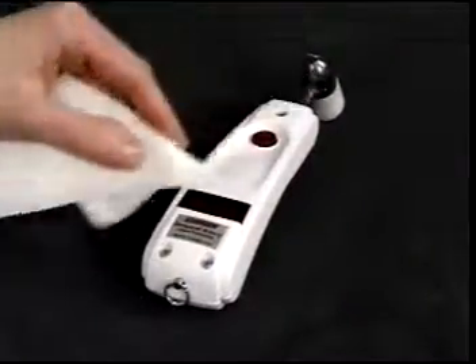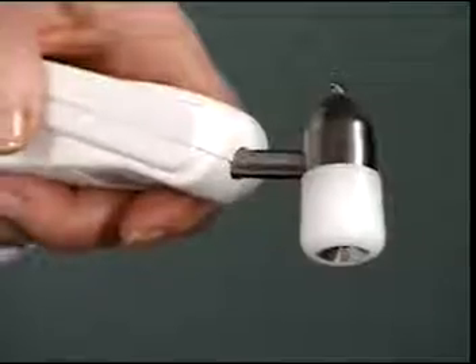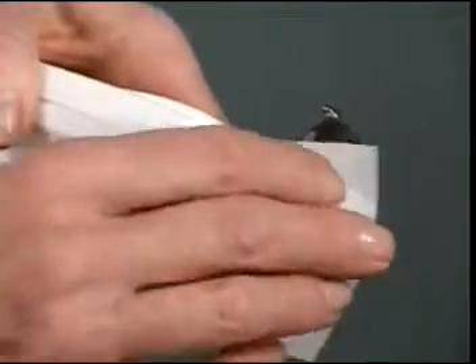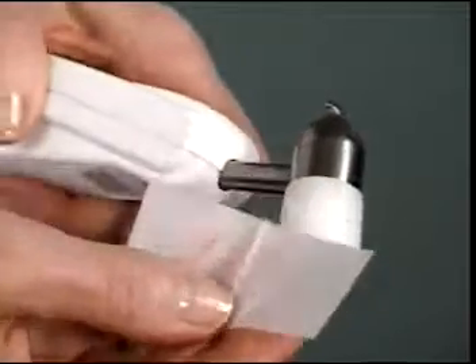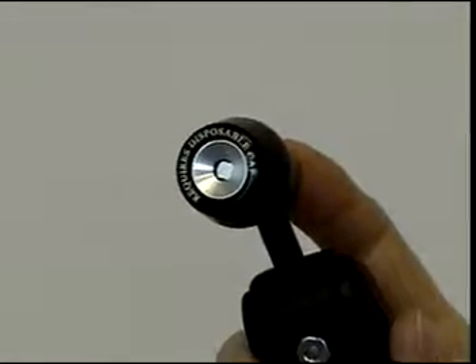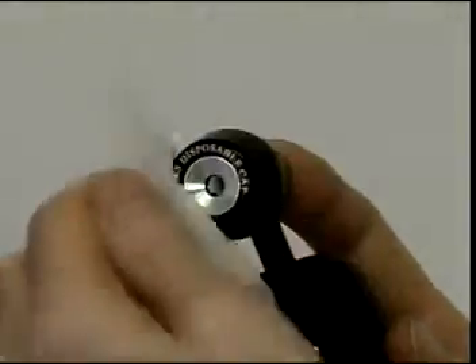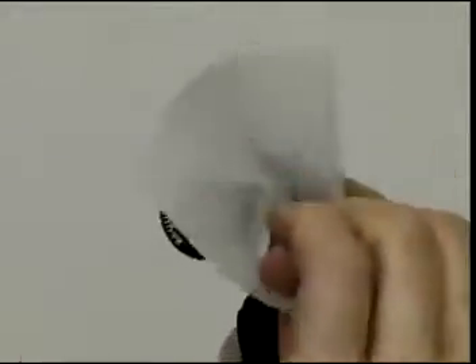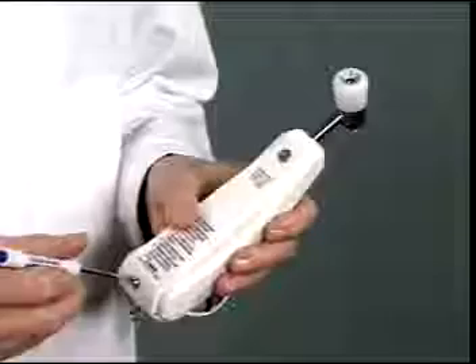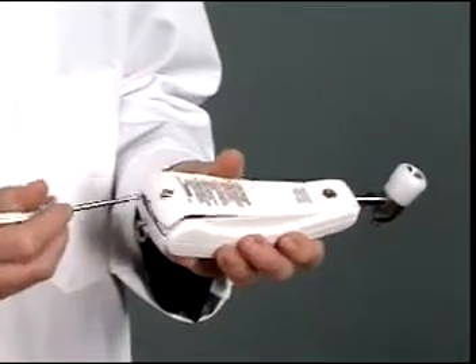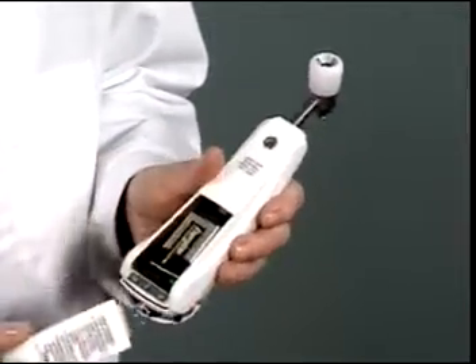The temporal scanner is very easy to care for. It can be cleaned with any hospital-approved disinfectant, alcohol, even bleach solutions. The probe lens should be shiny clean. If not, wipe with an alcohol prep followed by a swab or sponge dampened in water to remove any residue from the alcohol. To change the battery, simply remove the screw in the back of the thermometer and replace the battery.